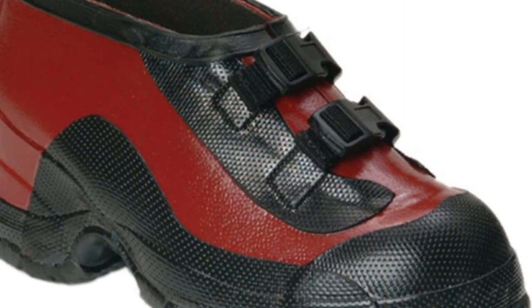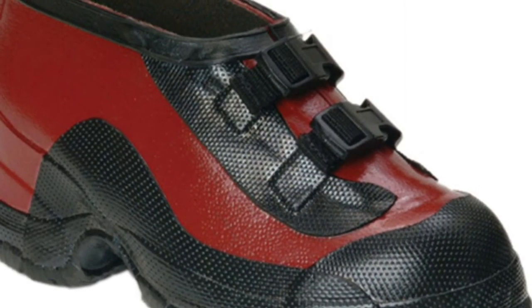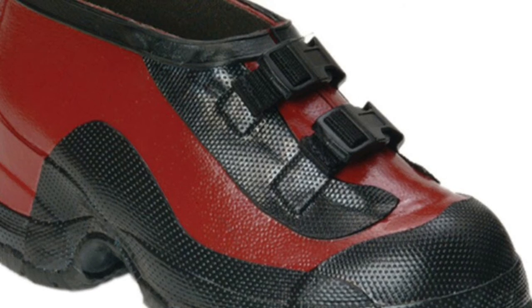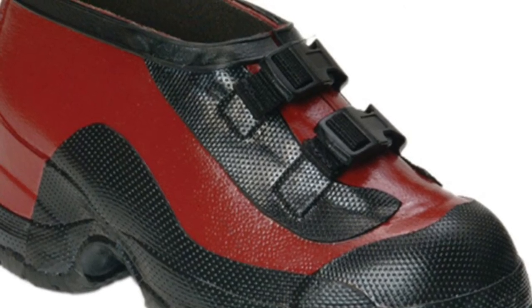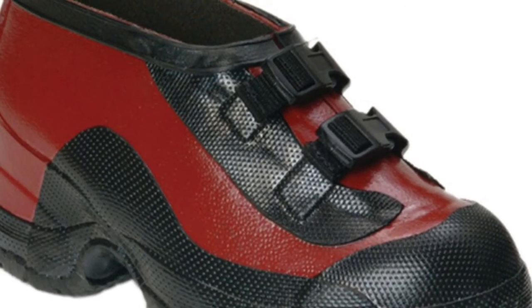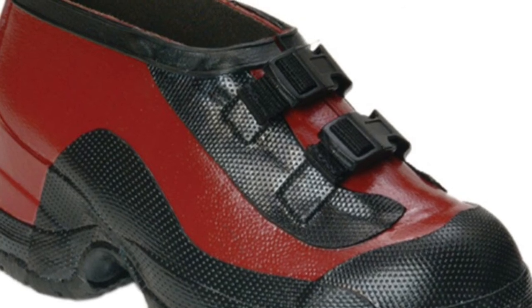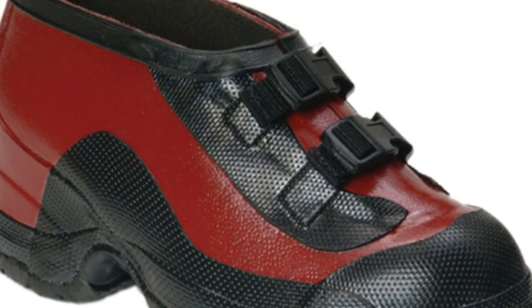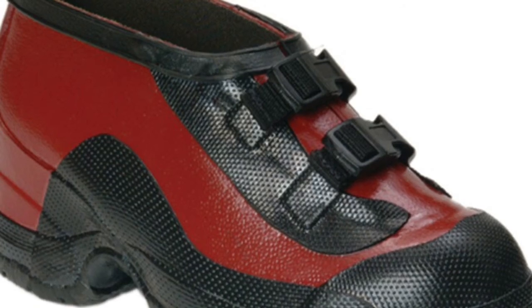Heavy-duty leather footwear or dielectric footwear, or both, provide some arc flash protection to the feet and shall be used in all exposures greater than 4 cals. Footwear with an arc rating is not available. Normally the employee's feet are less exposed than the hands or head due to the proximity of most tasks.